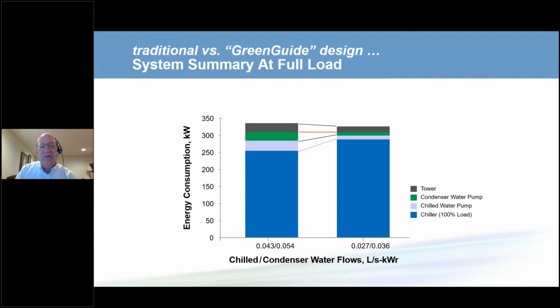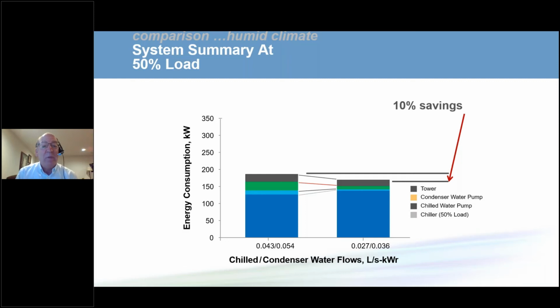But this is at design conditions. What happens at part load conditions? As we reduce the loads, the cooling tower can make cooler water. The difference in chiller power comes down. And what we see is that the ASHRAE GreenGuide flow system actually saves more energy at part load conditions than it does at full load conditions.